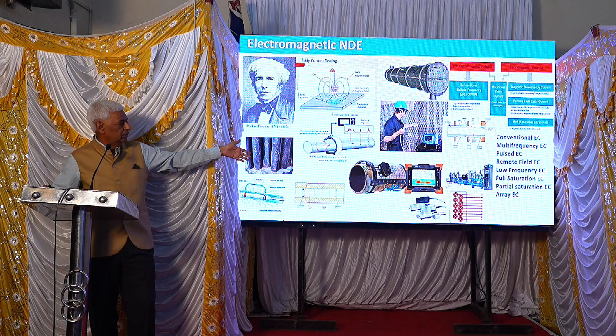Conventional eddy current could not do a good job of carbon steel heat exchanger inspection. That is when we got techniques like remote field eddy current, low frequency, full saturation, etc.